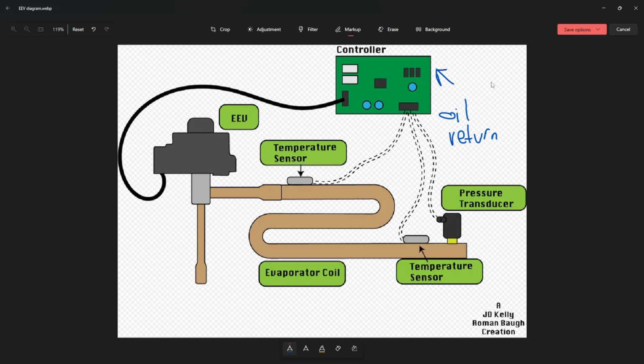Oil return is a whole different beast. We're not going to talk too much about oil return mode, but just know that this pressure transducer right here is used for dedicated things like oil return mode. It's also used for things like freeze protection. So if the evaporator coil drops below a certain pressure, this board knows that that coil is going to start freezing up, so it'll go into what's known as freeze protection.